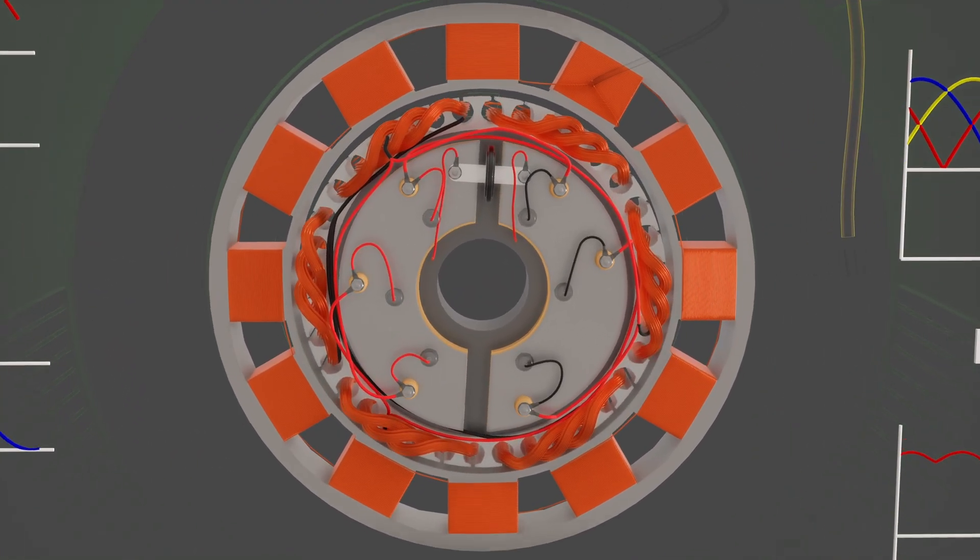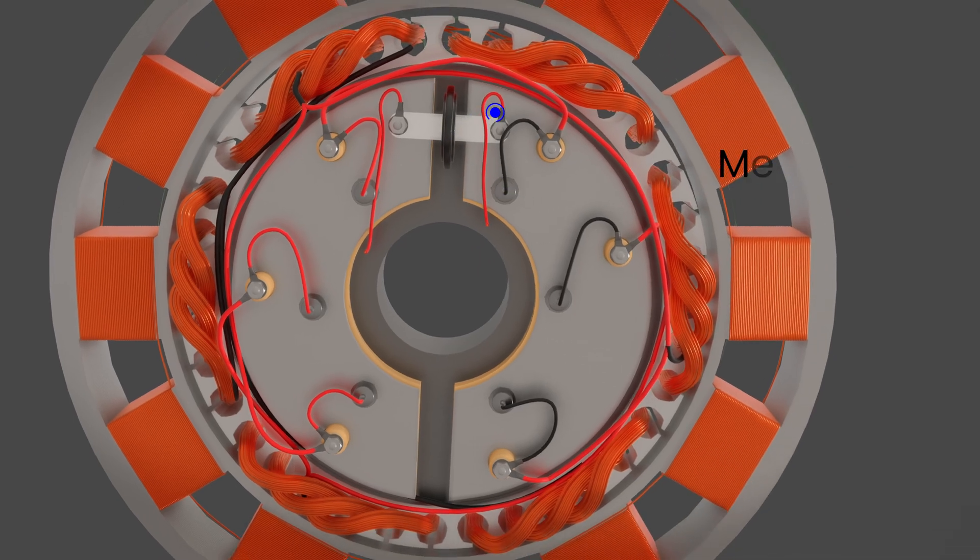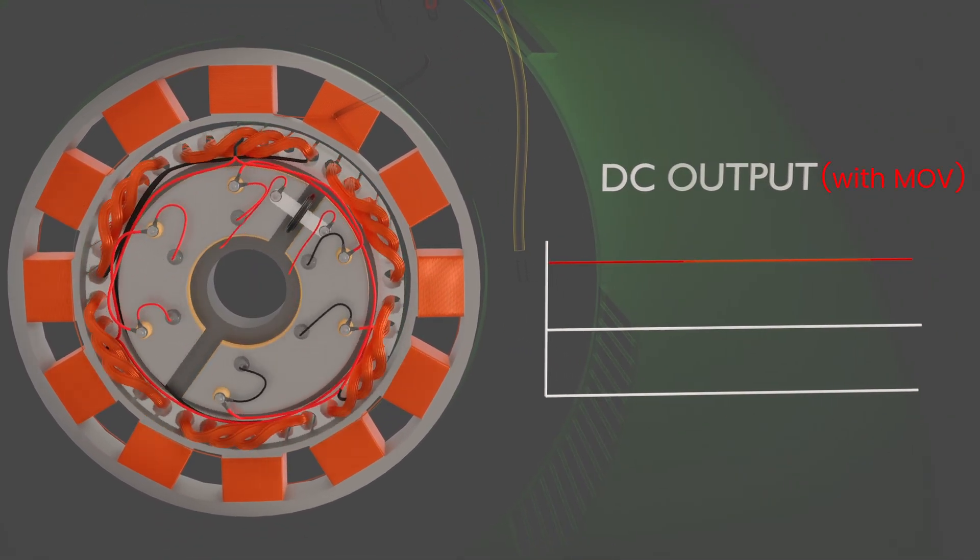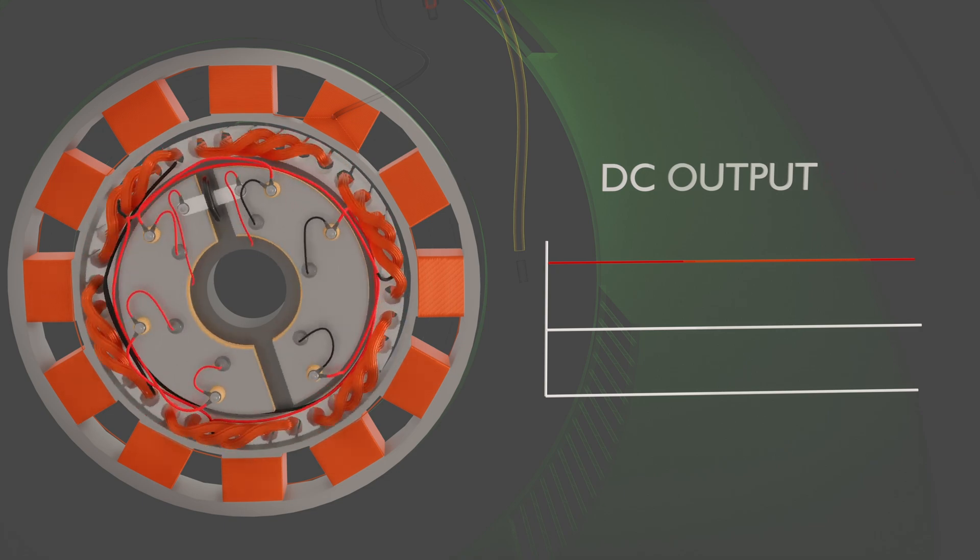For additional ripple reduction and protection against voltage spikes, a metal oxide varistor, MOV, is connected across the DC output. The MOV acts as a surge suppressor, clamping excessive voltages and protecting the rectifier diodes and main field winding from damage.